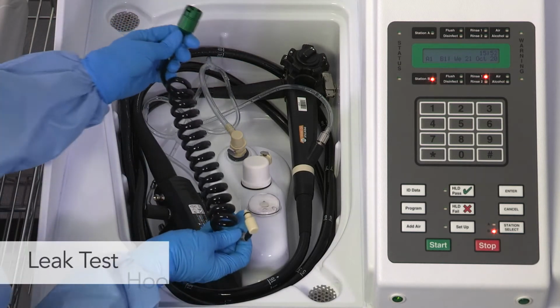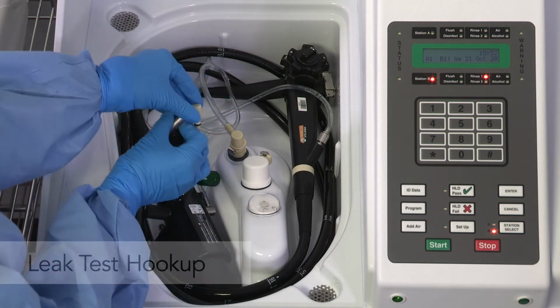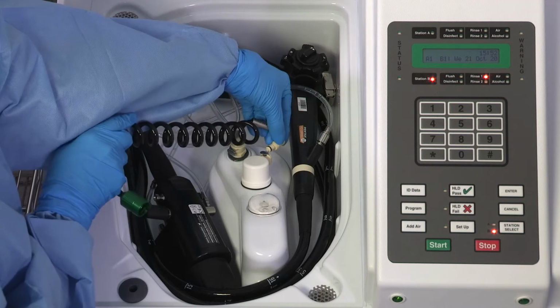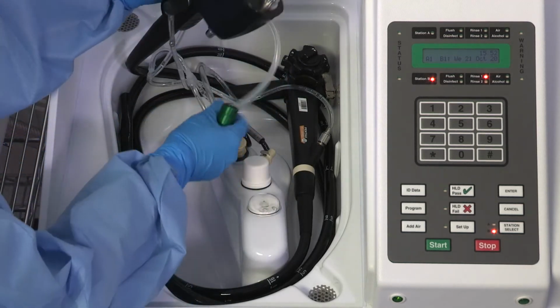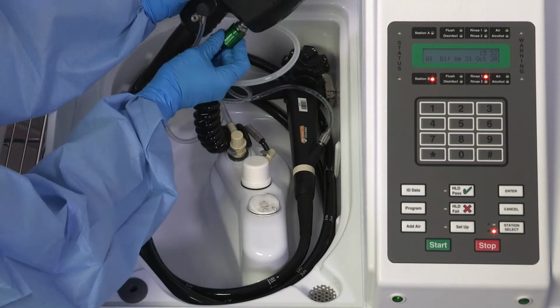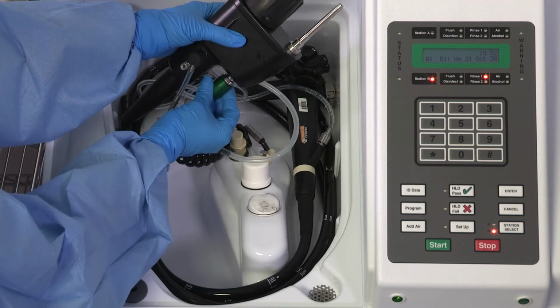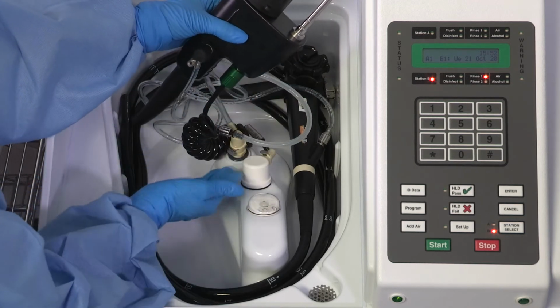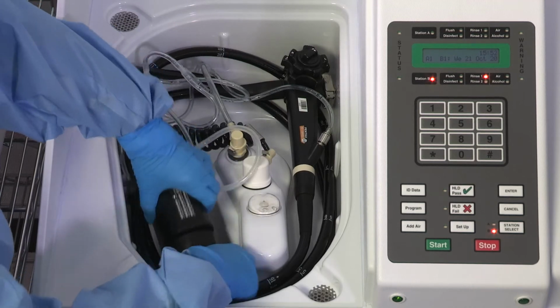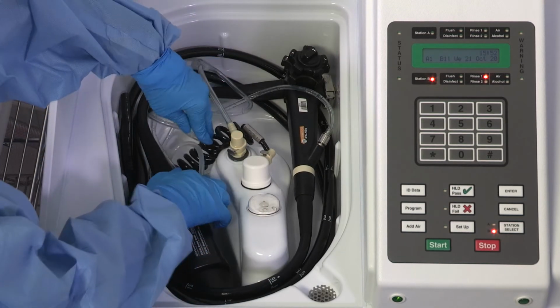To connect the Pentax DSD leak test hookup, connect the hookup to the basin's leak test connector. Align the slot on the hookup with the endoscope's venting connector. Push on and turn clockwise to engage. Always refer to the provided hookup IFU.